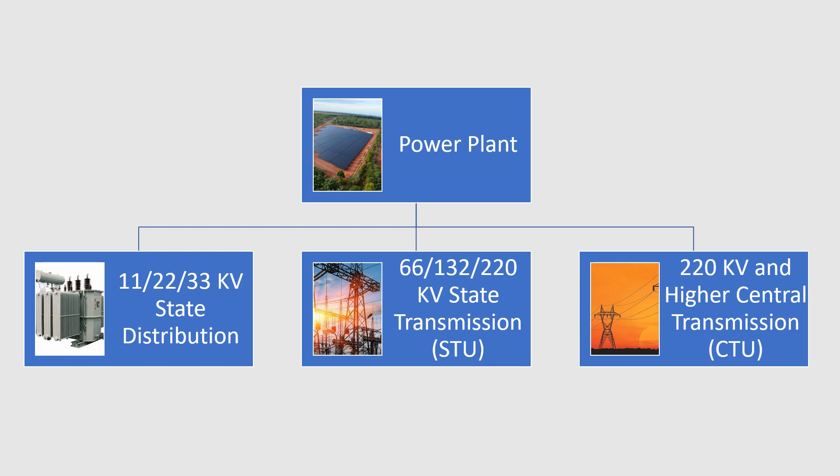Similarly, if the power plant size is slightly bigger — somewhere around 50 megawatts or up to 100 megawatts — these power plants are generally connected to the state transmission utility at a voltage level of around 66 kV, 132 kV, or 220 kV.